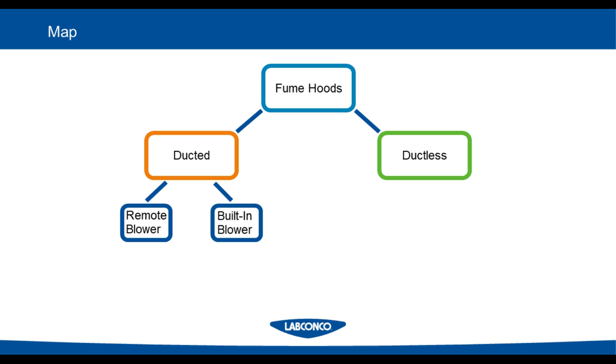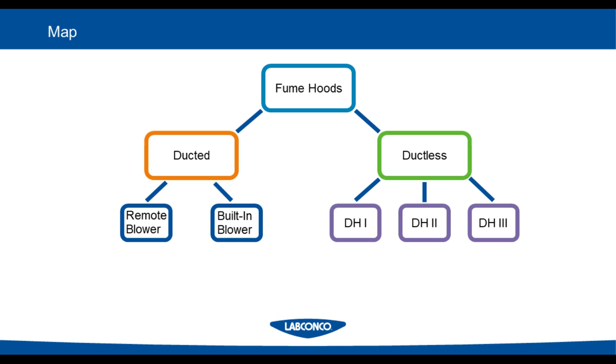So that was ducted fume hoods, and the other form of fume hoods that we're going to talk about are the ductless fume hoods, and these come in three types. You have the DH1, the DH2, and the DH3 setups. So ductless enclosures, as they sound, have no duct, which is a great benefit. And how they are able to do this is through carbon filtration. These filters capture the chemicals that are being brought through them and are able to recirculate clean air into the lab space. Most of the time, your application will need to be reviewed by the manufacturer or someone involved in that to make sure that it is applicable to what you're doing in the lab, because not every application is suited for this. It's not a substitute for every hood.